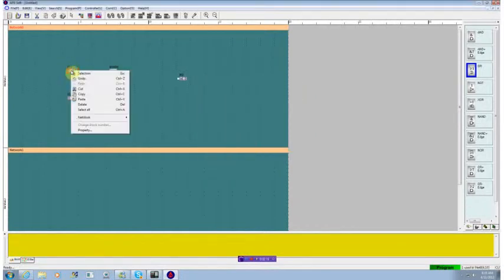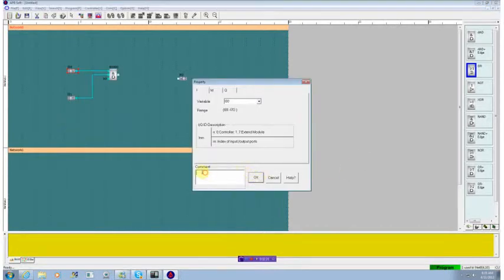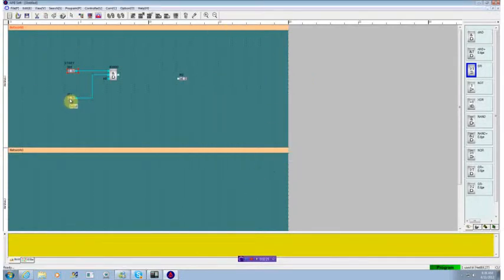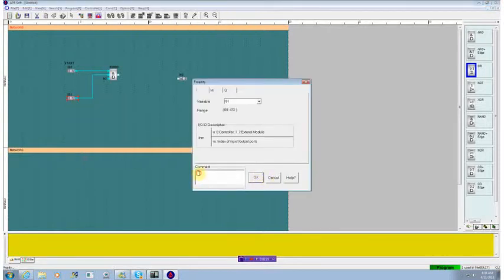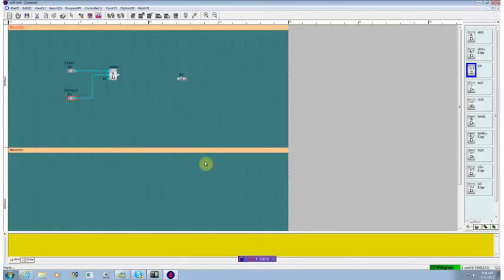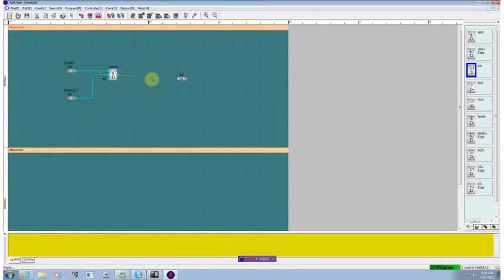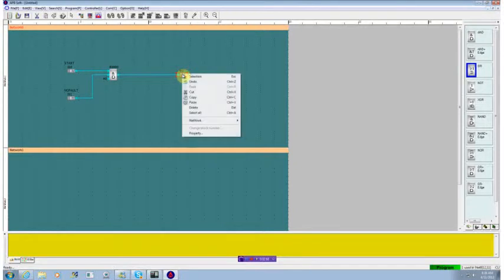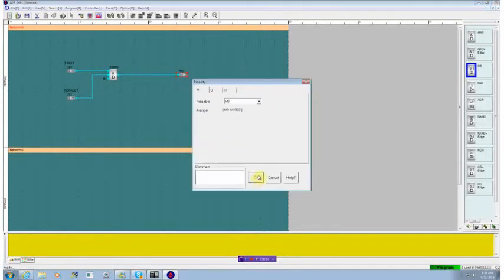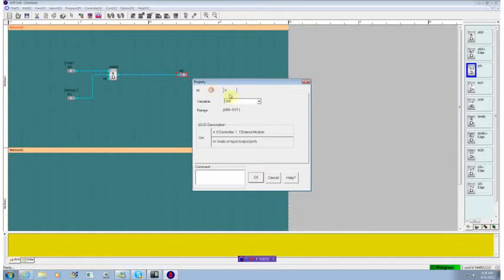The input, though, we want to call that the start button. And this one, we'll call that no fault. So we want to be able to set it up so if there's no fault and start button's pushed, then this output will go to this point. Now, the output point is currently at M0. M would be one of the internal memory registers. We want to change that to be a physical output, in this case, output zero, and we'll call that motor.